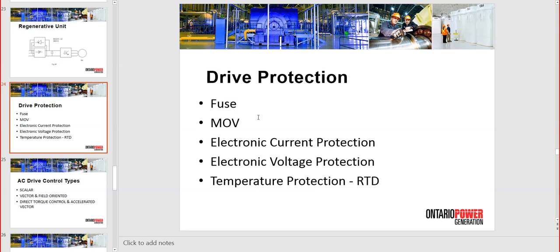Okay, protections on the drive: fuse, MOVs, electronic current protections. Now the fuses are for diodes and thyristors. They don't protect IGBTs. MOVs, metal oxide varistors, are for overvoltages on the diodes or thyristors, or even IGBTs. We need to know that IGBT is very touchy. It's gonna deteriorate in a pulse that is overvoltage in 25 microseconds. So we need to have very fast protection. That's why there is electronic current protection in the inverter.